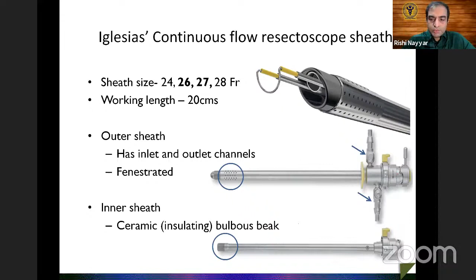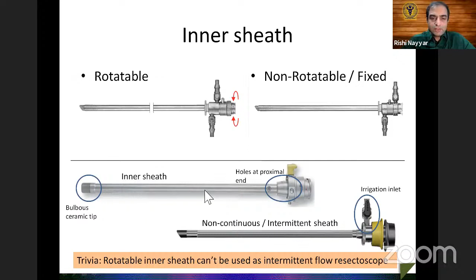One is rotatable and one is non-rotatable. Rotatable means that when you rotate the inner sheath, the outer sheath does not rotate with it, and therefore it results in less shear or traction on the urethral mucosa when the outer sheath is inside. Whereas the non-rotatable fixed sheath would also move the outer sheath along with it, and therefore it would produce a curvilinear shear on the urethral mucosa, and may be more traumatic in that sense. The inner sheath of the rotatable type of resectoscope is not the same as the non-continuous irrigation sheath, and they are not synonymous with each other.